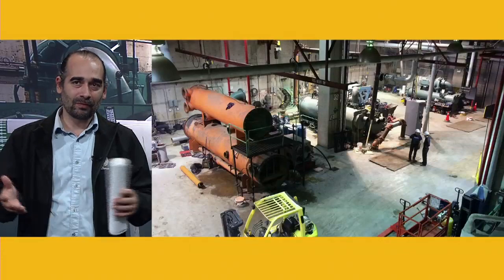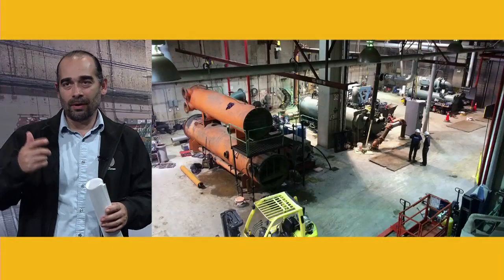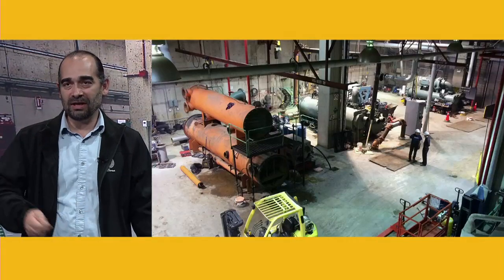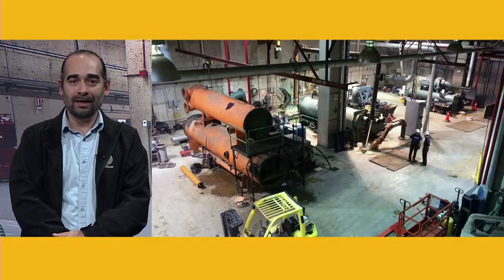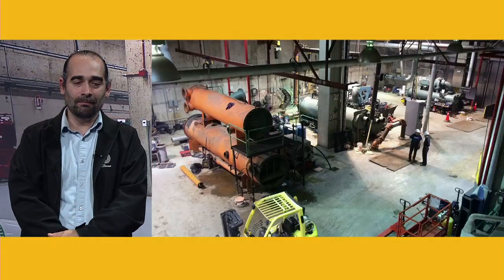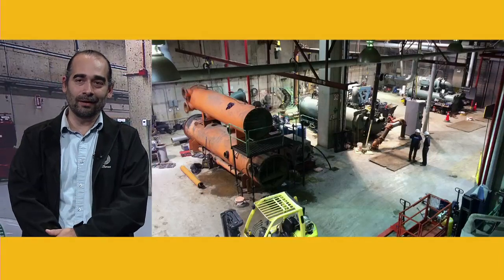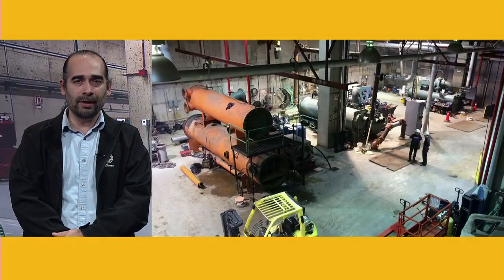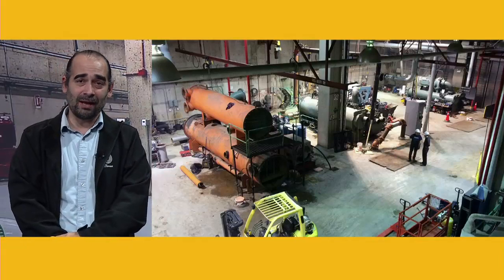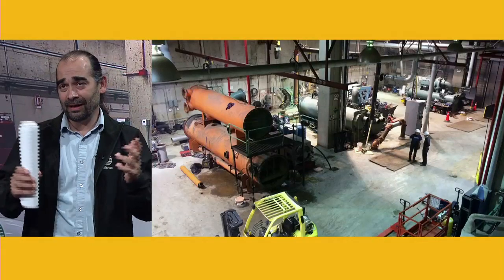Yeah, sure. We have to remember first that the stadium was built for a 2-week event, the Olympics. So all the equipment was sized to go through that event, not for day-to-day use. When I arrived at the stadium before the project, the people there would start up a 2,500-ton chiller at the beginning of June and let it roll 24 hours a day till September. And worse than this, I saw two of these chillers rolling, because in baseball mode or some event mode, they were using two of them all summer long. So we really needed to rethink that chiller plant.